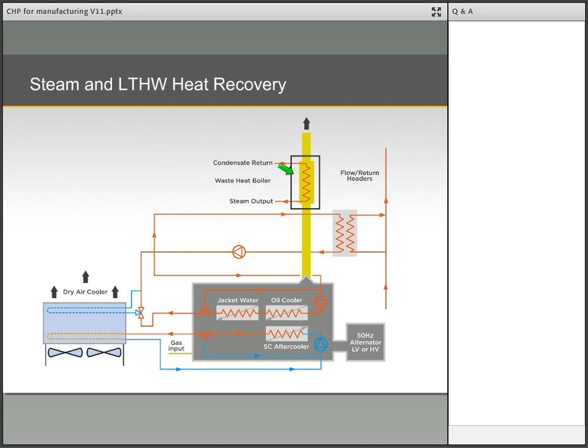Medium temperature hot water can also be generated from the exhaust flue system in a similar way. LTHW can still be recovered from the engine water jacket, and the system efficiency can be further enhanced by fitting an economizer downstream of the boiler to pick up any residual heat in the exhaust gases as LTHW.